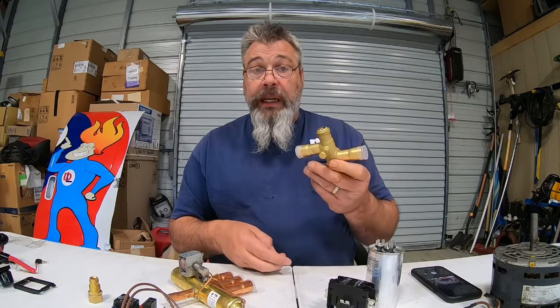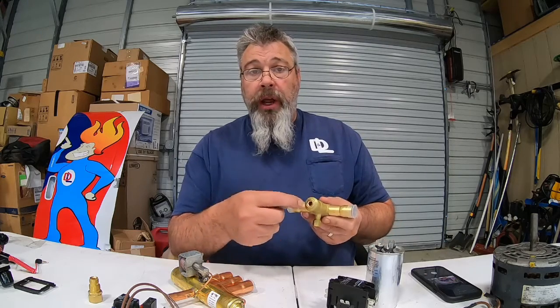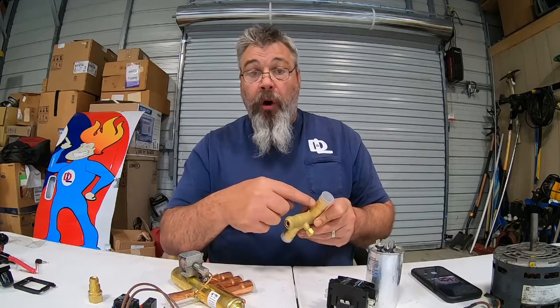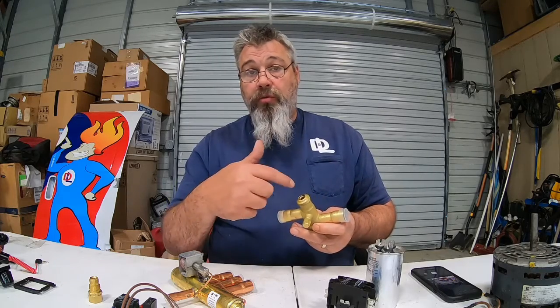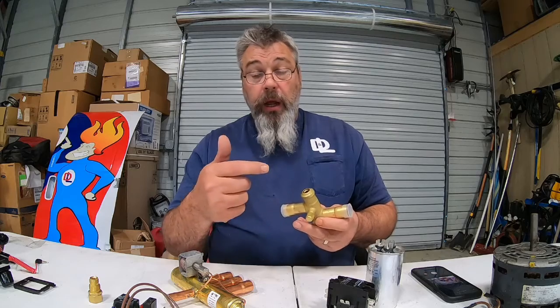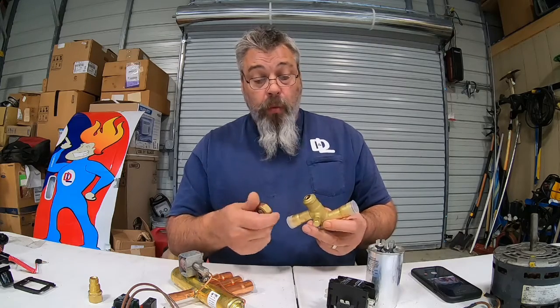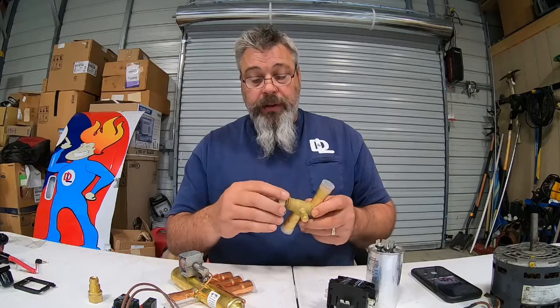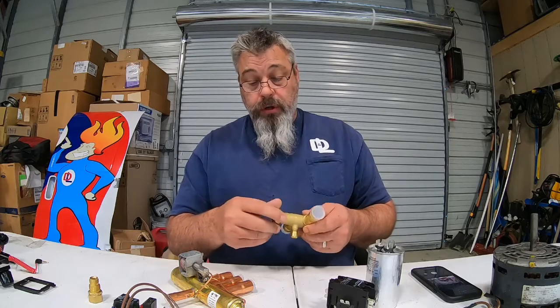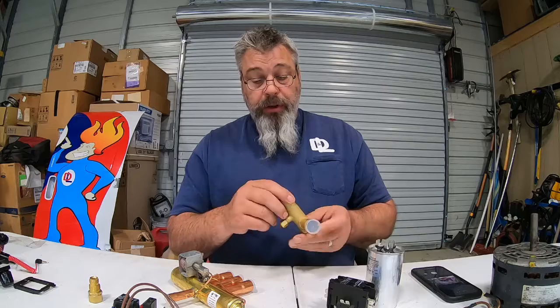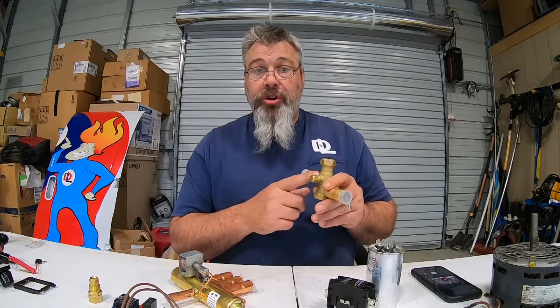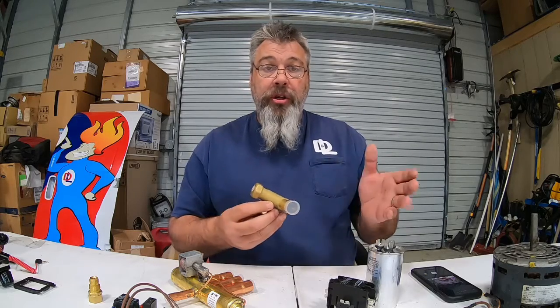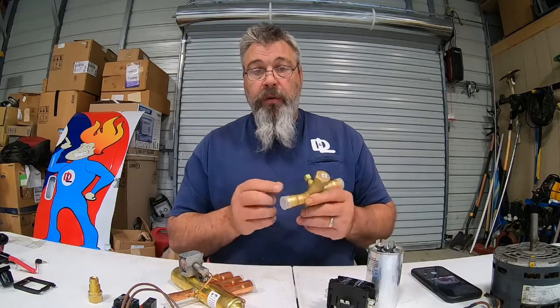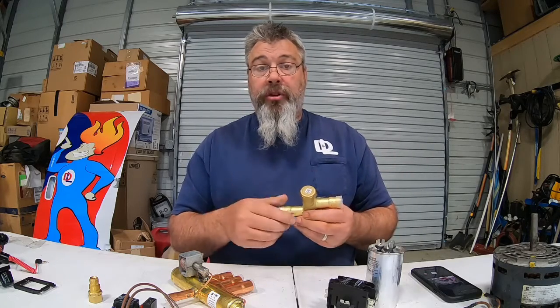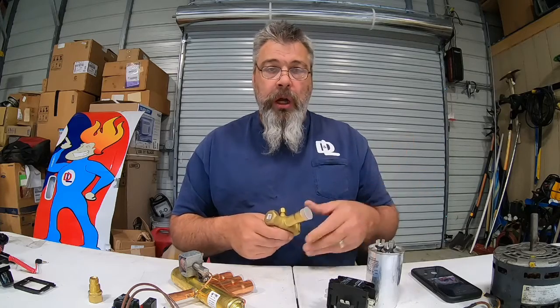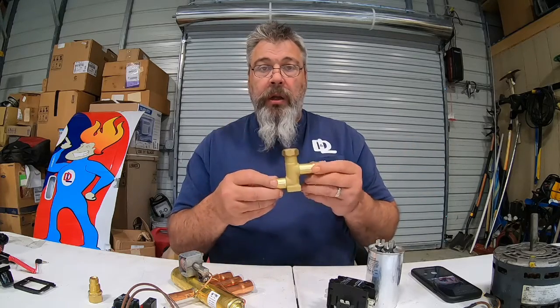We have seen a lot of these leaking. Basically, it's just an Allen head screw that screws down in here and closes the valve off. It has rubber O-rings inside there, and they wear out after time. Once they're open, they should not have to be closed again unless your unit has to be serviced. So we always check these out. There are two of these. One's called the suction service valve, and the other one is called a discharge or liquid line service valve. So if you ever hear a technician say your liquid line service valve's leaking, that's going to be your small line. Your suction line is going to be your big line.